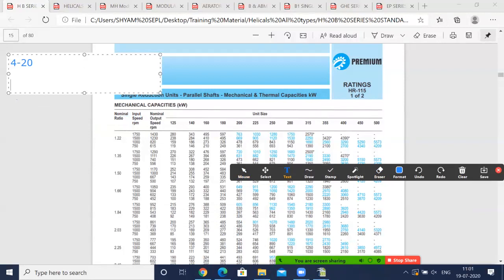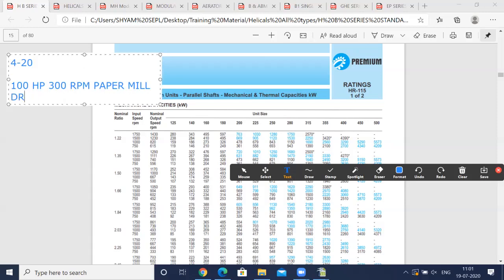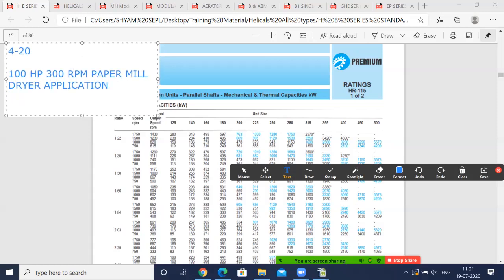So for 4, if there is an inquiry of 100 HP and 300 RPM, and it's a paper mill application. Paper mill basically means high speed, and these are the dryers. So they will tell you it's a dryer application. In a dryer application, let us do the selection first for a 4:1 or 5:1 ratio, at 300 RPM.